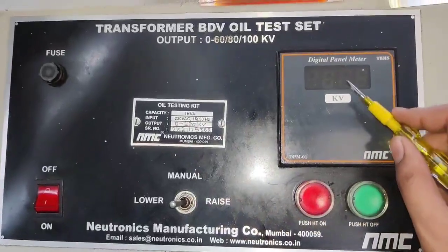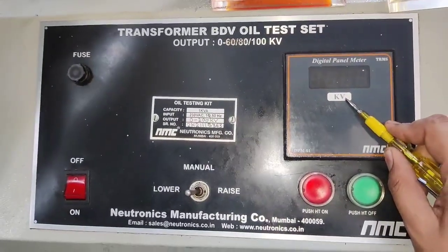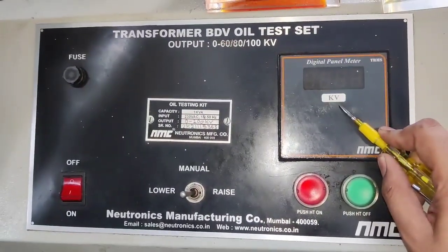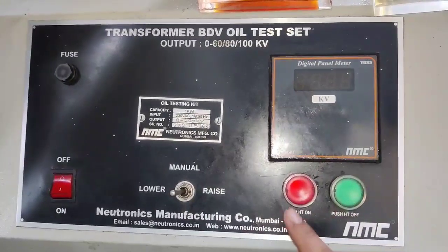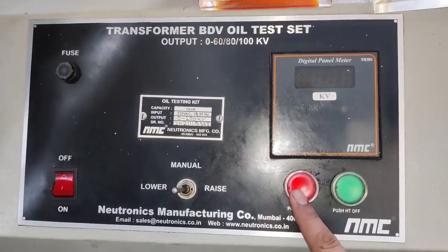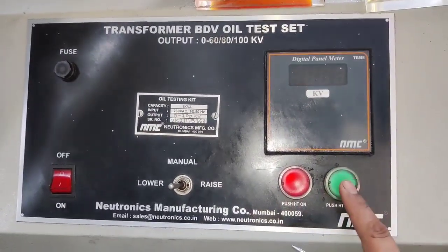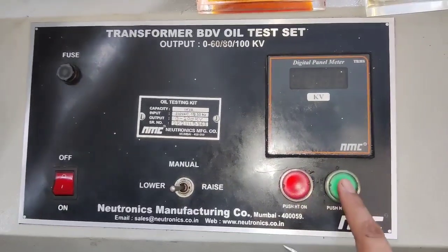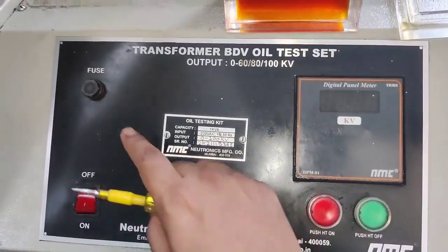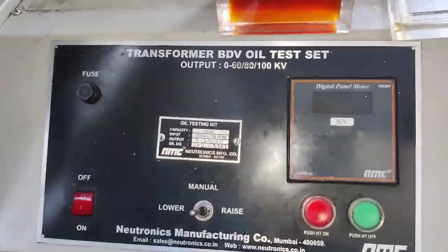Also, this is the kilovolt meter, in which you can see how many kilovolts are showing. This is a start push button by which our test will start. This is a stop push button, and we also have one fuse.